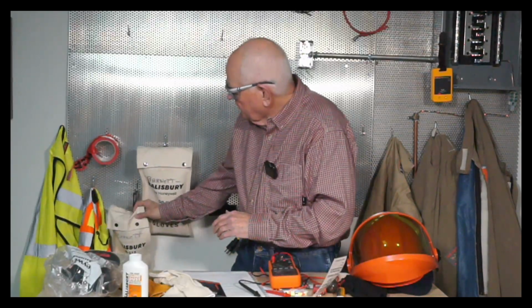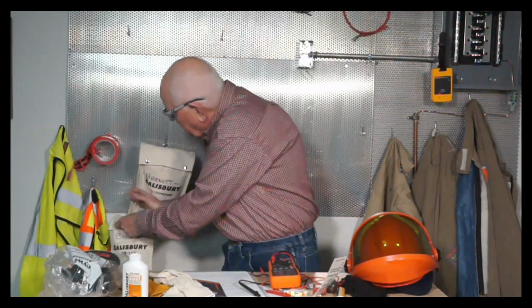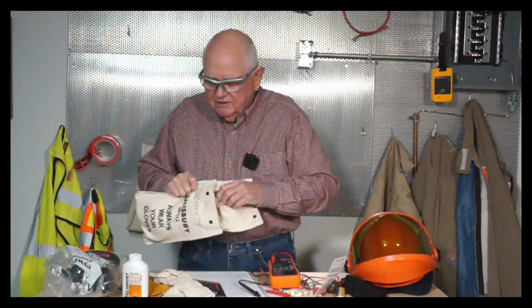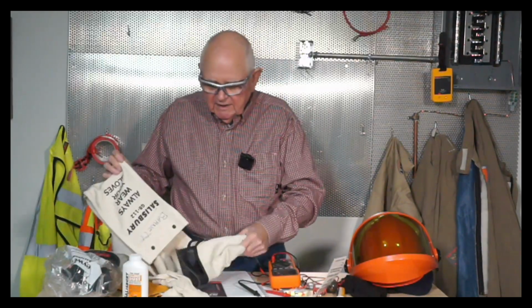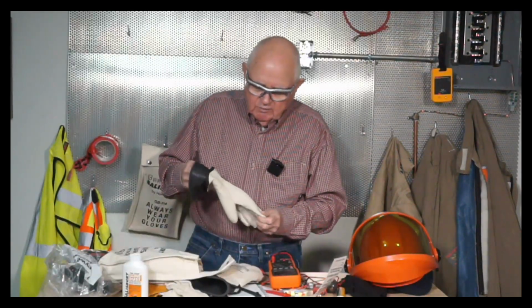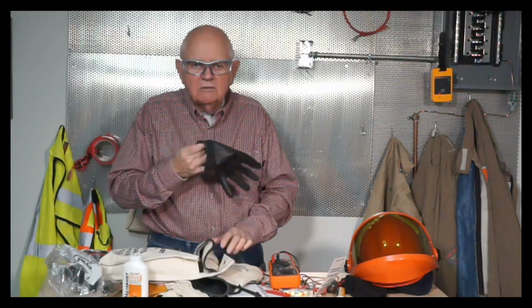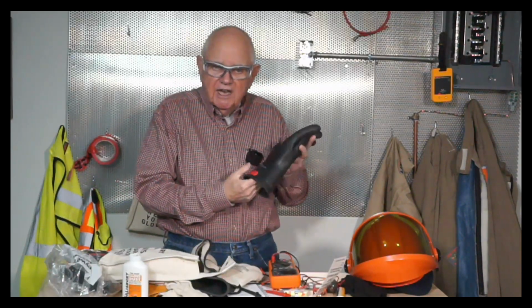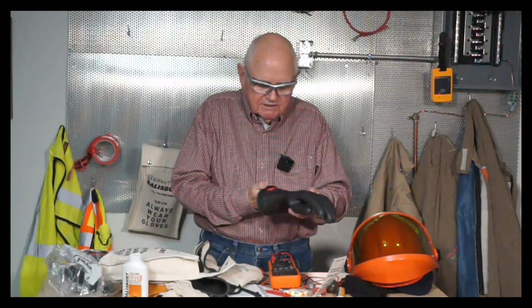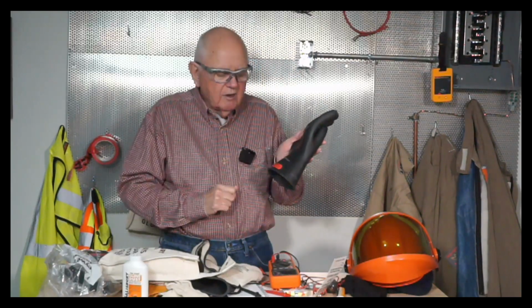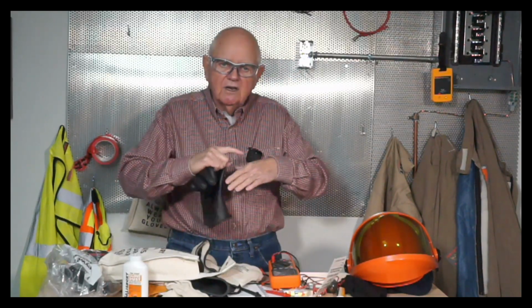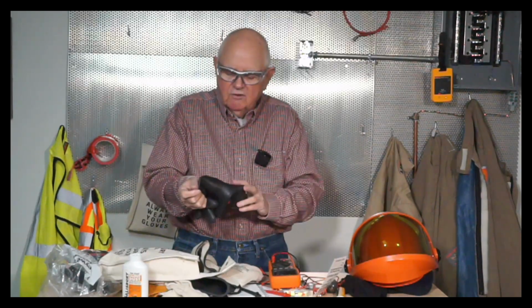Quick review then, a refresher for rubber gloves. Let's take a pair of, I believe these are class zeros in here. Yep. So my class 0 on the label, it's red, which tells me that, but I don't need to memorize it. It says class 0 on it. I verify my test date and the size of my glove. I take a soft cloth tape, wrap it around my hand. That's the size of my rubber glove.